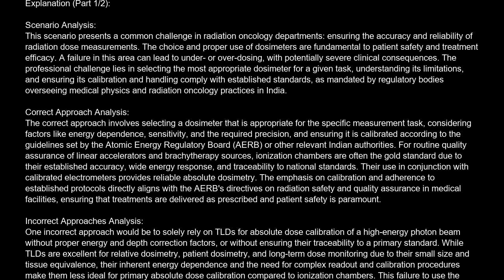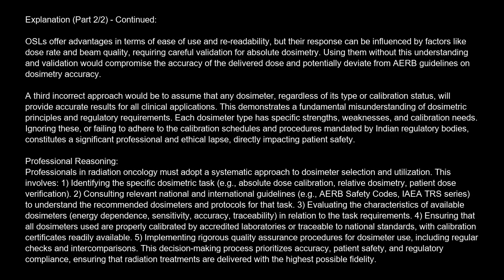Another incorrect approach would be to use OSLs for routine output calibration of a linear accelerator, without understanding their specific energy response characteristics, and without a robust calibration protocol. OSLs offer advantages in terms of ease of use and rereadability, but their response can be influenced by factors like dose rate and beam quality, requiring careful validation for absolute dosimetry.